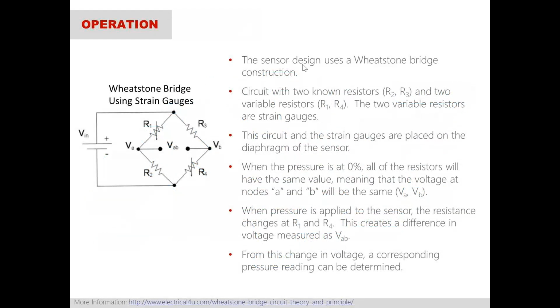The actual pressure sensor operates on a Wheatstone bridge design. A Wheatstone bridge is a series of resistors that are printed essentially on the backside of a flexible diaphragm. As the diaphragm senses the process pressure and the pressure increases, it will cause that diaphragm to flex. As it flexes, you have these two variable resistors, R1 and R4 here, and their resistance will change as well. That change in resistance is what you're measuring, ultimately changing the voltage of the circuit. We then amplify that signal and convert it into a more usable signal for operators, such as the 4 to 20 milliamp signal. That's one of the most commonly used methods for obtaining a pressure measurement out there in the field.